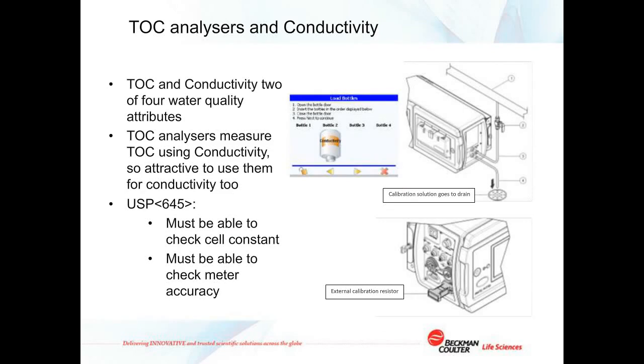As these TOC analyzers in fact use conductivity to measure the TOC, it's attractive to use them to measure both TOC and conductivity. However, the Pharmacopoeias insist on two calibration steps for conductivity analyzers. The first one is to make sure you can measure the cell constant of the conductivity analyzer using a certified traceable solution. And the second one is to check the accuracy of the conductivity meter electronics using an external certified resistor.